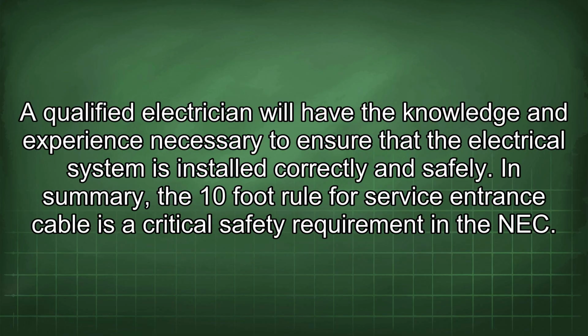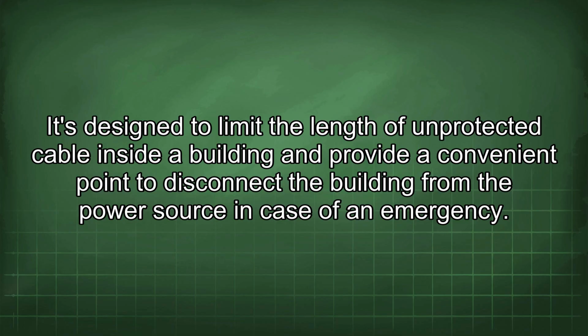A qualified electrician will have the knowledge and experience necessary to ensure that the electrical system is installed correctly and safely. In summary, the 10-foot rule for service entrance cable is a critical safety requirement in the NEC. It's designed to limit the length of unprotected cable inside a building and provide a convenient point to disconnect the building from the power source in case of an emergency.